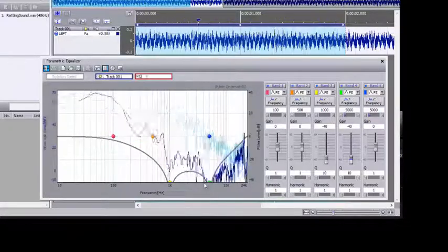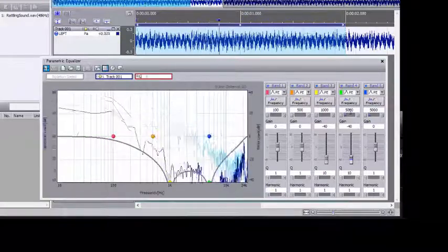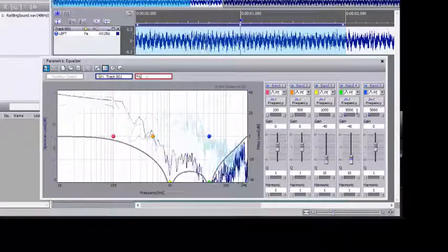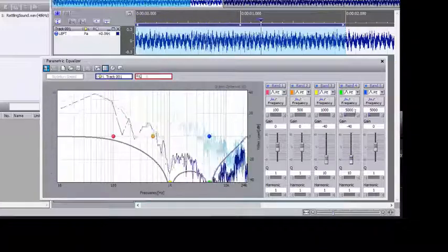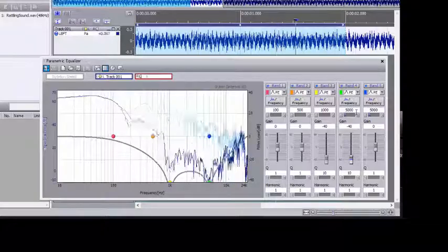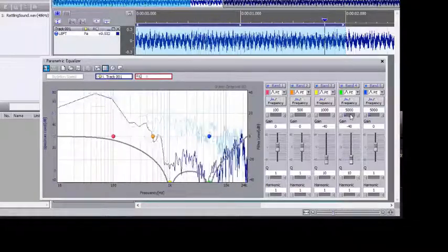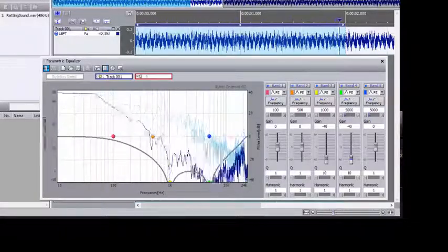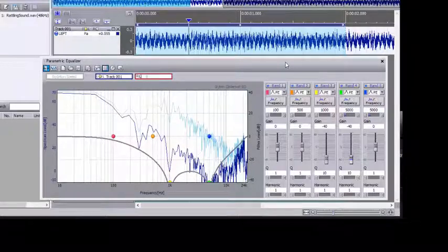When applying the high range of filter, you found that you cannot hear the tapping sounds. See the high range of frequency. It was 5 kHz. We set the frequency at pinpoint earlier. However, generally you don't know the frequency of a target noise. Next, we will show you how to find the frequency of target noise.